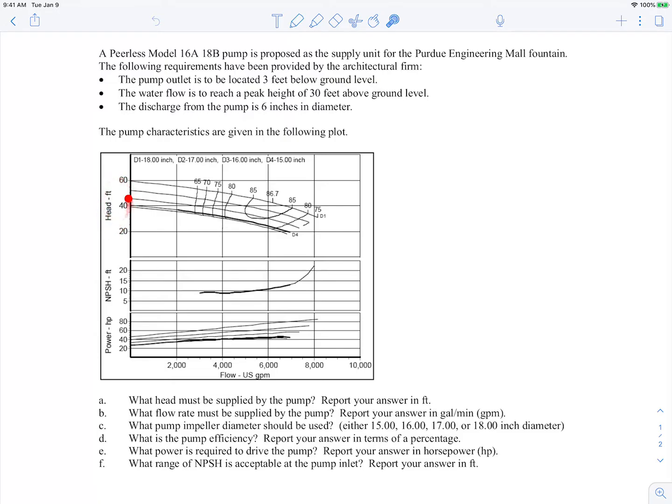You can see here we have the head rise that we get from the pump as a function of the flow rate through the pump. This is the NPSH and the power of the pump. And if you look on this plot, you'll see that there are actually four impeller diameters given: 18 inch, 17 inch, 16 inch, and 15 inch. That's D1, D2, D3, D4.